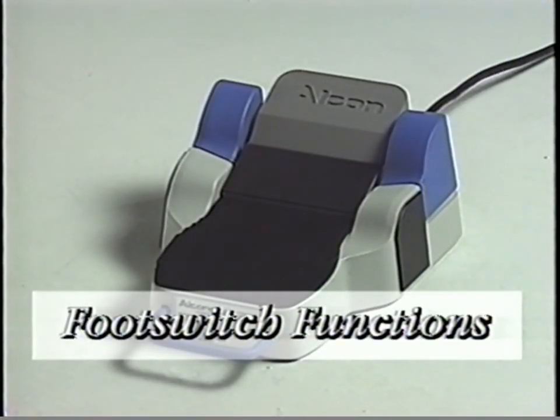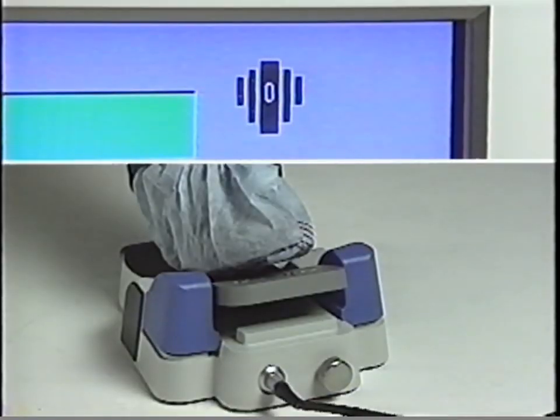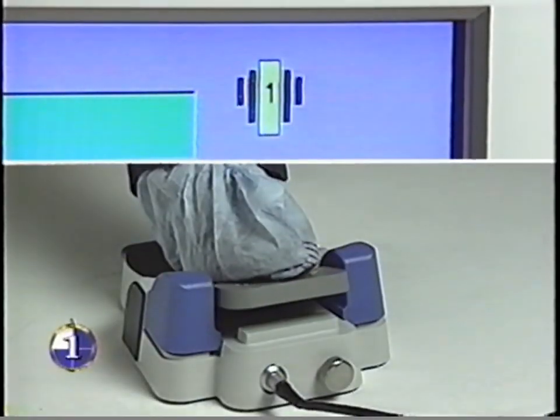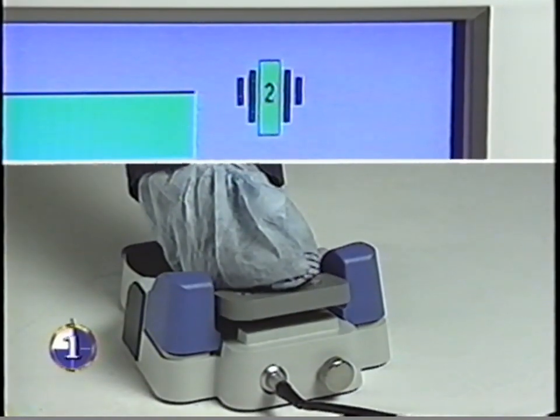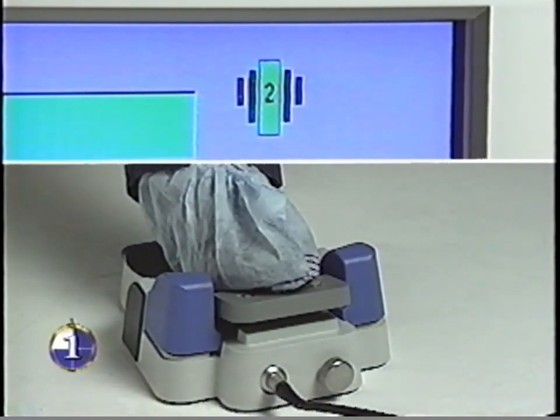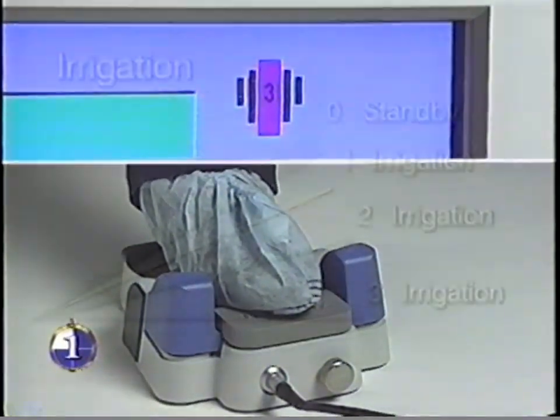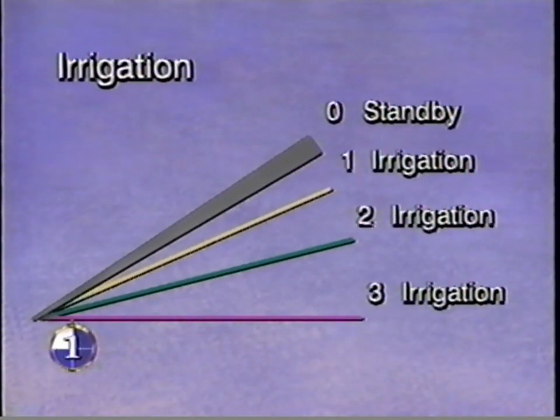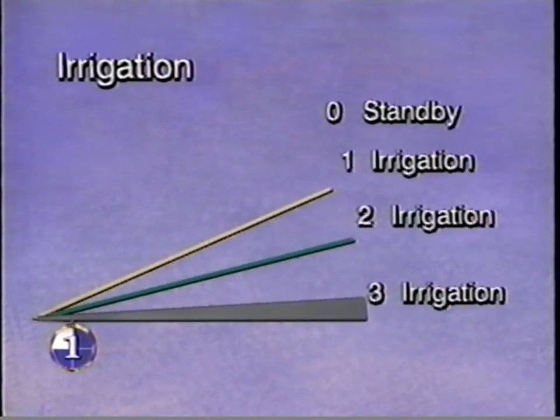The surgeon can control all functions within the operating modes using the foot switch. Each foot switch operating position lights up its corresponding number and color on the control panel. Position 0 is standby in all functions and lights up in white. Position 1 is yellow. Position 2 is green, and position 3 is fuchsia. In the irrigation mode, positions 1, 2, and 3 are used solely for irrigation.